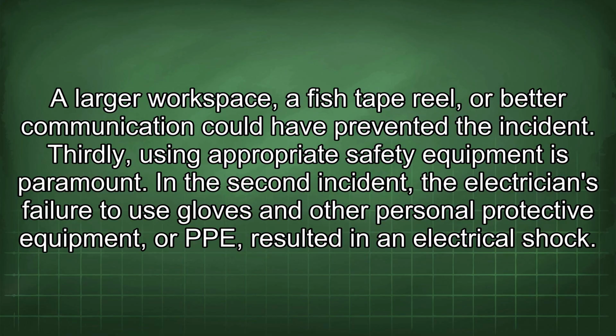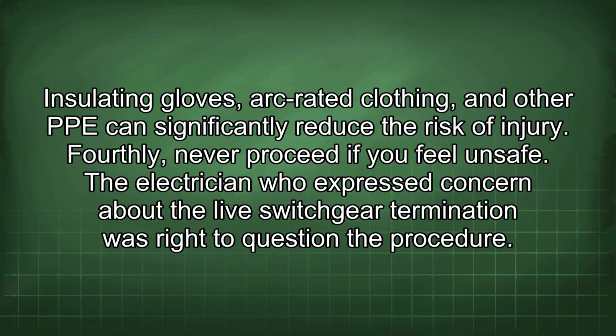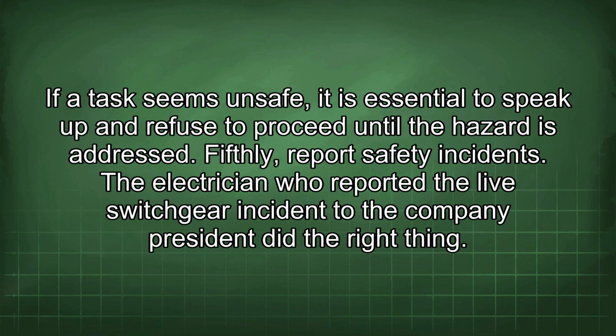Thirdly, using appropriate safety equipment is paramount. In the second incident, the electrician's failure to use gloves and other personal protective equipment, or PPE, resulted in an electrical shock. Insulating gloves, arc-rated clothing, and other PPE can significantly reduce the risk of injury. Fourthly, never proceed if you feel unsafe. The electrician who expressed concern about the live switchgear termination was right to question the procedure. If a task seems unsafe, it is essential to speak up and refuse to proceed until the hazard is addressed.